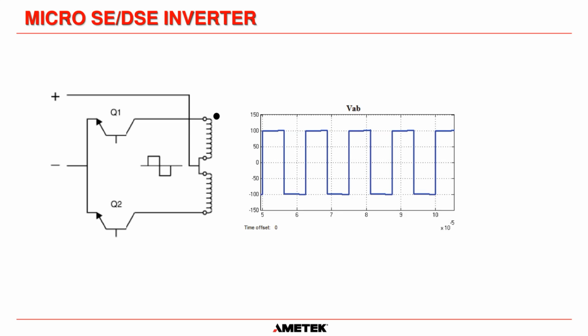So this is how we use IGBTs in our Micro-ferro, or any system that has a ferro-resonant transformer in it that has a microprocessor. So we have two types now. We have what's called the Micro-ferro SE or the Micro-ferro DSE. The only difference between the two is the new DSE has the same mimic screen as our DPP pulse width modulated technology. Okay, but what we're doing is we still have positive and negative on the left hand side.